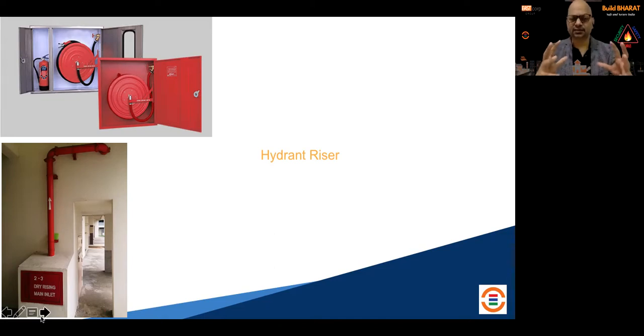So there are a lot of installation errors, defective or poor installations, because thought is not being given. The hose reel tap has a globe valve, but if you cannot operate that valve fully, then there is no water flow coming into the hose reel. You need to see that the valves inside the shaft or riser are able to operate fully.